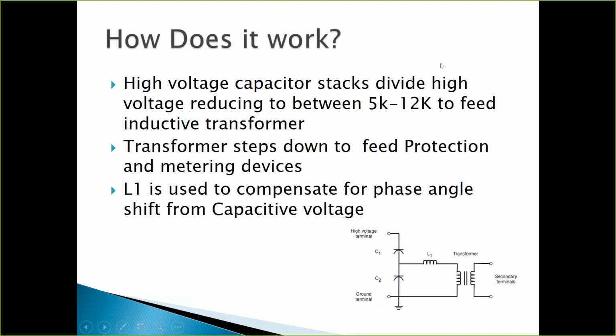Here's what it does. So here we have the line voltage hooked here, and we reduce it down to 12, 5 kV to 12 on 100 kV and 230 kV. This is at 12,000 volts is what we use. We also, on the coupling capacitor voltage transformer, have some ferroresonance suppression circuits in here and some drain coils. And what they're used there to dampen your signals that you may get from any type.